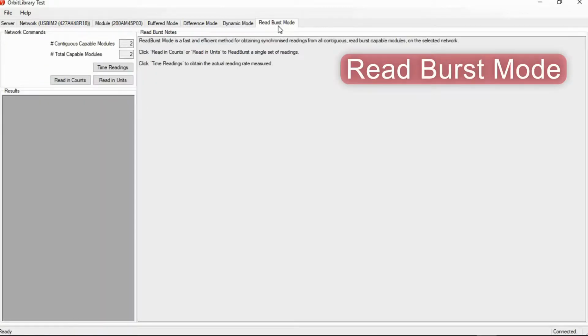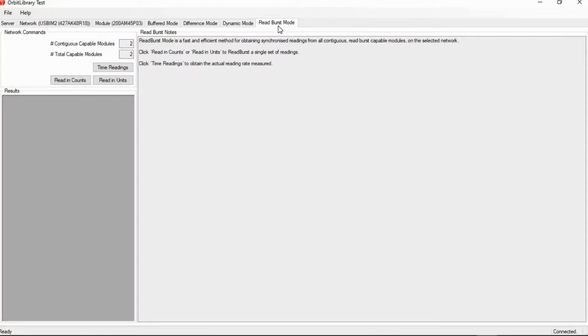So then the final tab is read burst mode. Now again, read burst is basically, if you send a read burst command to the Orbit network, it will send back one single dynamic reading of all the probes and all the modules on the stack. So this is something that's a little bit handier where if you want to do a dynamic reading but don't want to go through all the setups, basically what you can do is have your computer or whatever device you have hooked up to the Orbit network and just have it rapidly send the read burst signal.